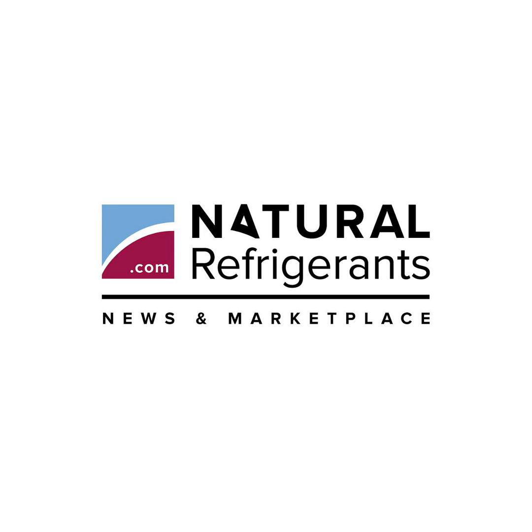The panels save us from putting out capital for end-of-life synthetic condensers when we plan to remodel the store in the near future anyway, Kolstad said. We can reuse the panels with the new transcritical CO2 rack. It's a win-win. Today, the panel system costs 10 to 20% more than a traditional air-cooled condenser replacement, Holzschuh said. However, he thinks it will become cost-neutral as manufacturing scales up.